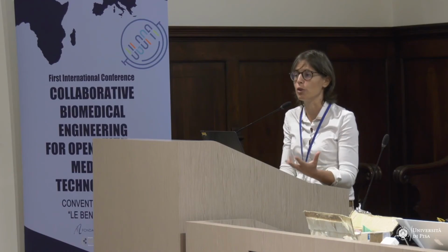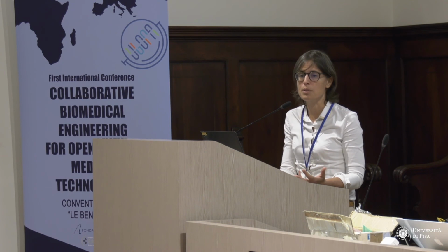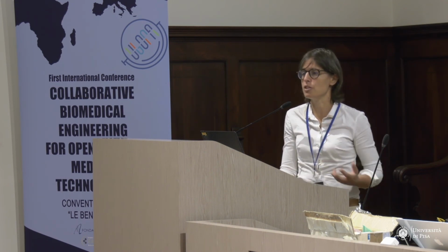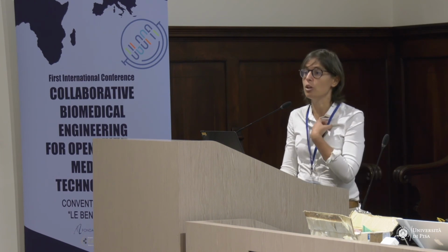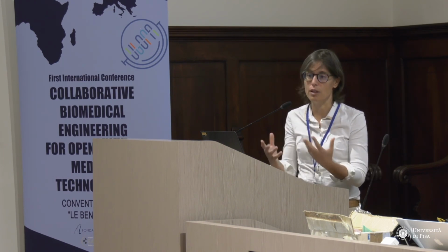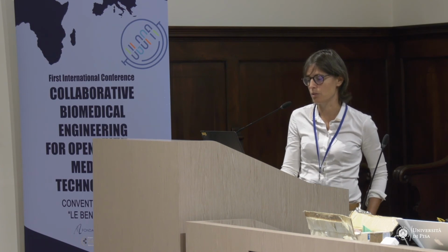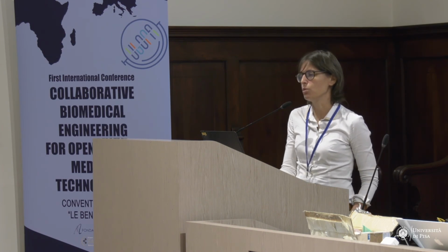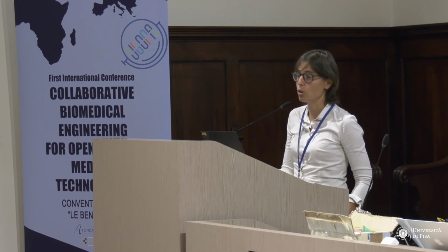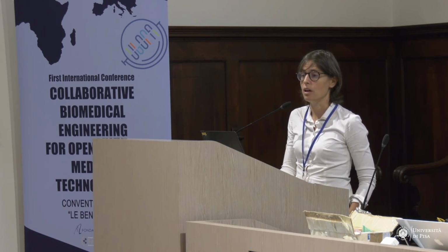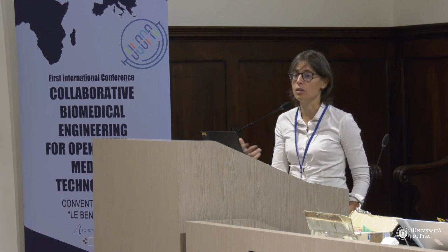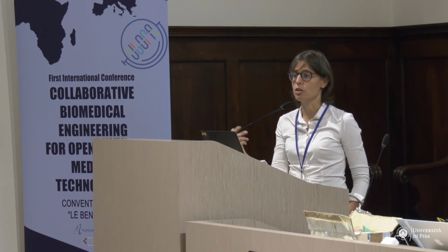It is not ethical to do it on patients if you're not sure of your design. So you try to use mock-ups, you try to use past data, you try to interview the physician, pretending you are a patient. So it is very unethical to use patients for this kind of usability tests. Of course, you need to interview and observe all the groups that we decided to have in our design. So if it is patient and caregiver, surgeon and nurse, you have to interview them all.